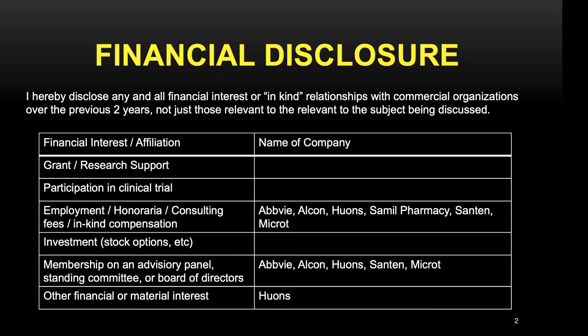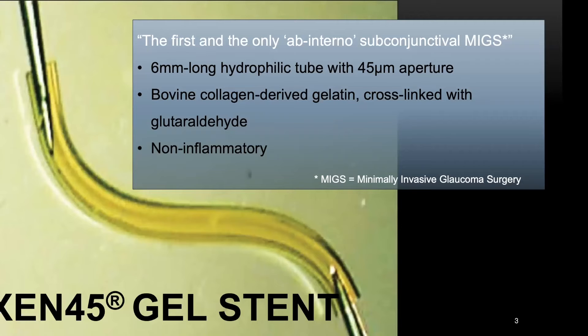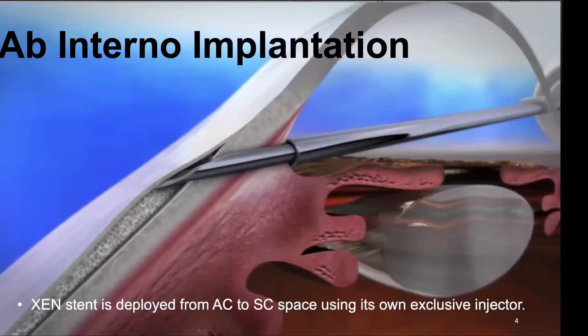The XEN45 Gel Stent is the first and only ab-interno subconjunctival MIGS device. It is a 6 mm long hydrophilic tube with a 45 µm aperture, made of bovine collagen-derived gelatin, which causes little tissue inflammation. The original XEN insertion technique suggested by the manufacturer is ab-interno implantation, where XEN is deployed from the anterior chamber to subconjunctival space using its own exclusive injector.